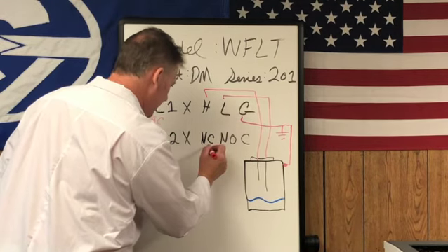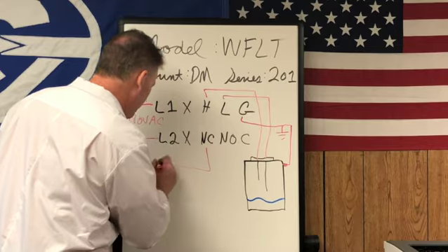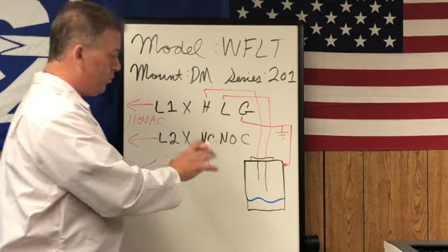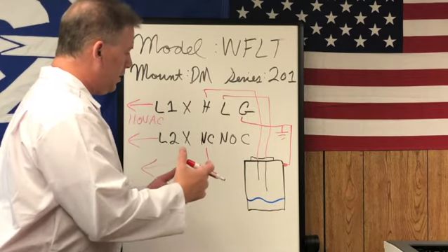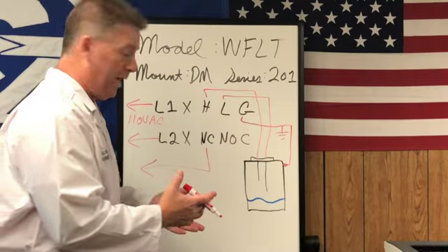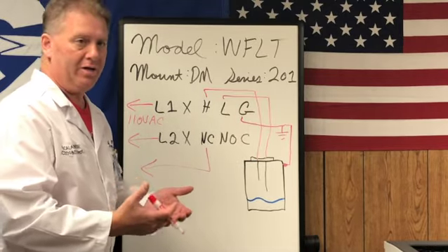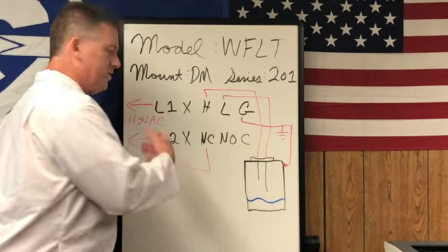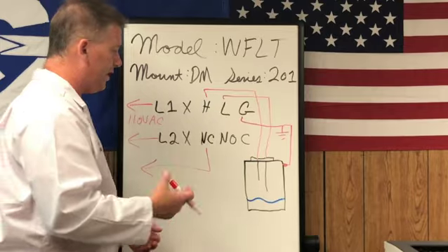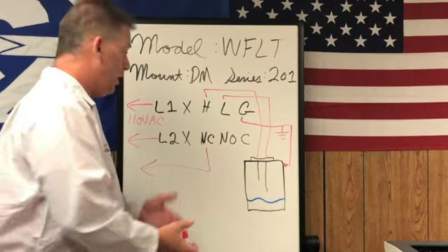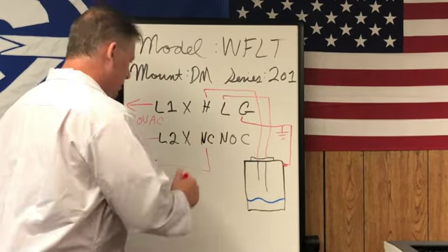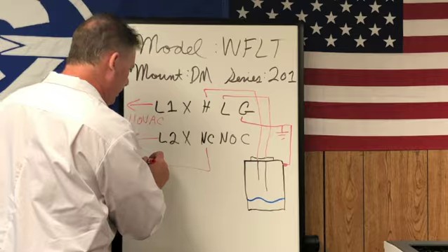Normally closed is going to go back to line power. The relay can handle, at 110 volts AC, 10 amps. At 220, it can handle 5. You just divide it in half. At 24 volts AC, it can handle 5 amps. So normally closed goes over here.